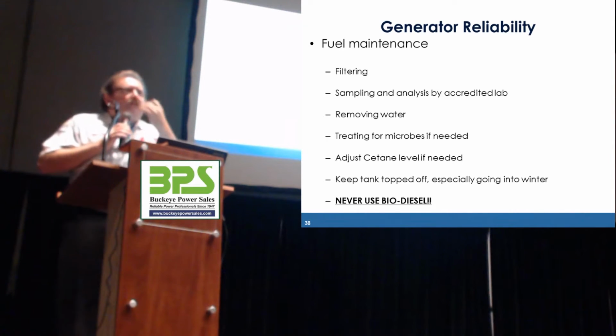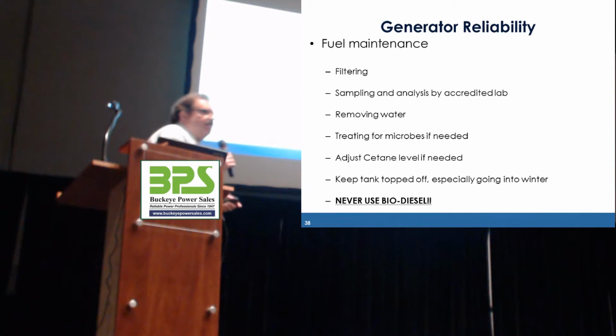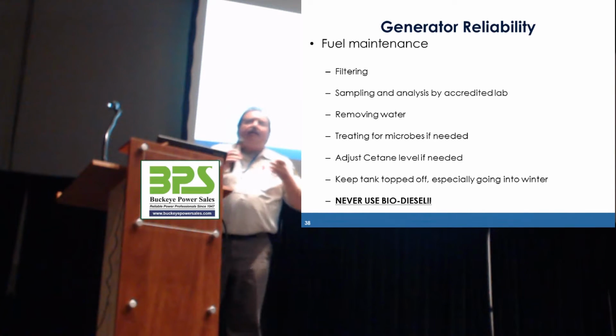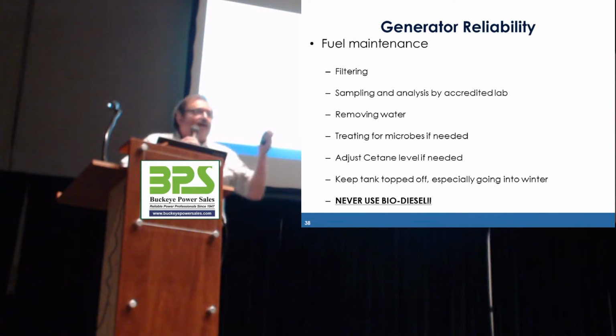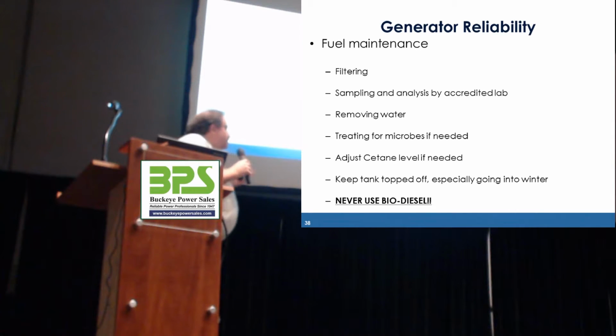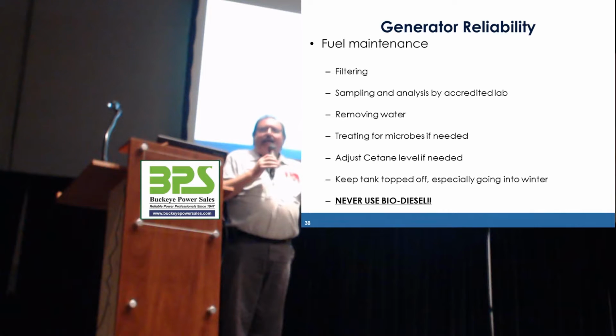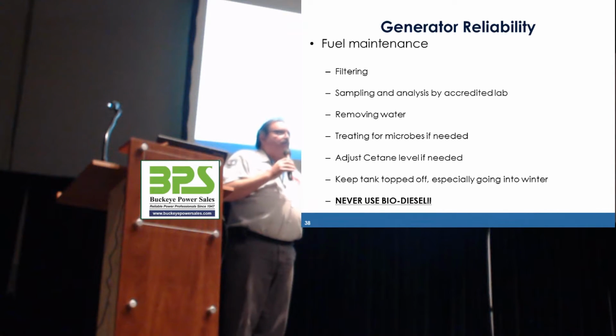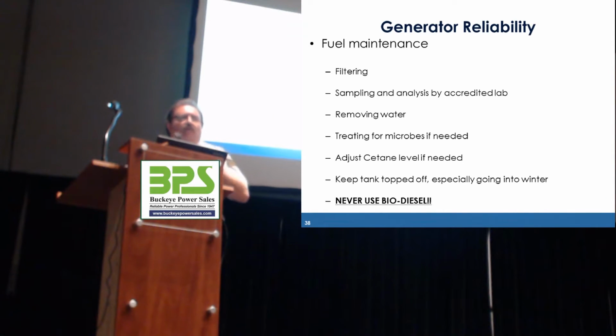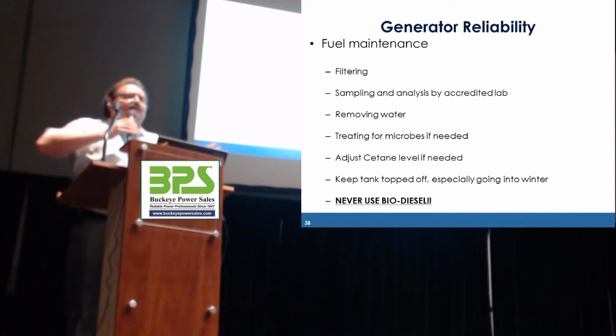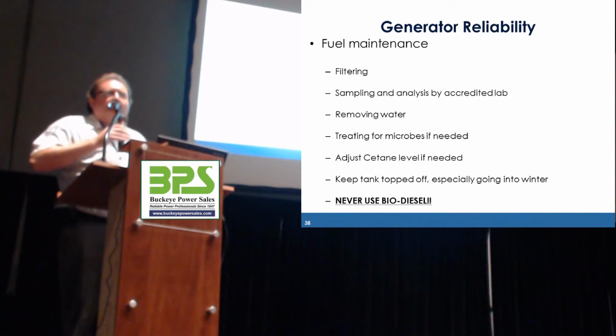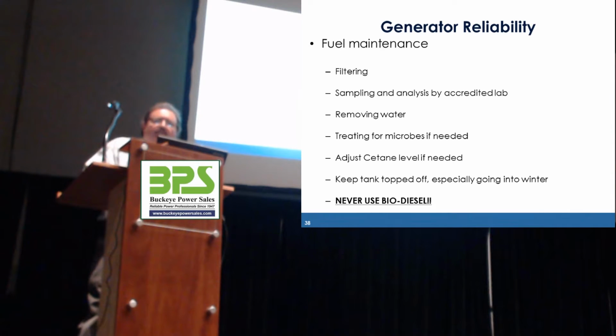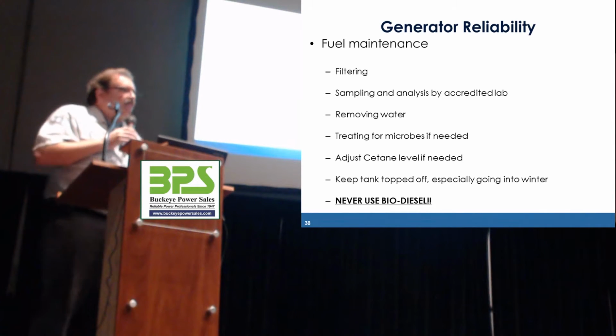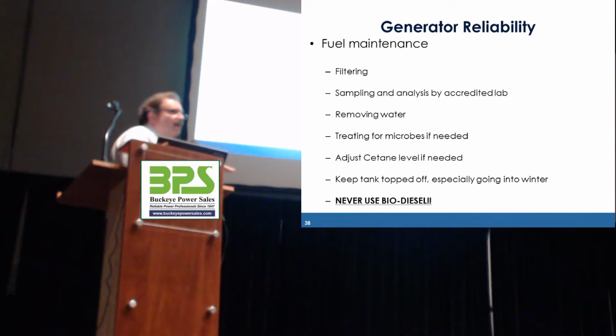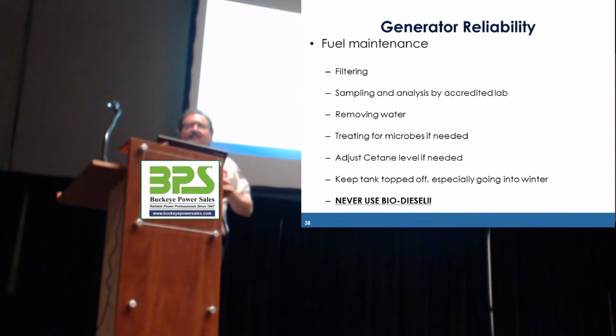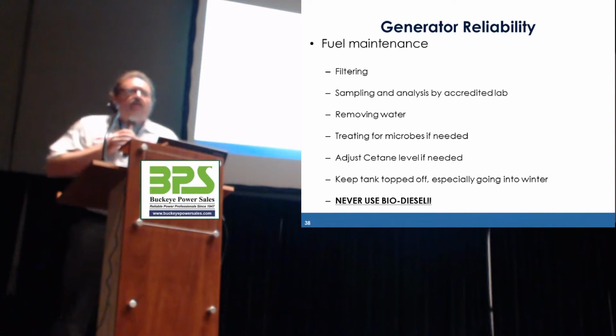and that's where more of the water comes in. So one of the best recommendations is, as you're getting ready to head into winter, so right now, make sure that your fuel tanks are at 90%. Never fill them to 100%, because if you get a hot day like today, it can expand too much and then purge out the vent, and then you have an environmental mess. So get them full to 90%. That will help alleviate some of that expansion and contraction.